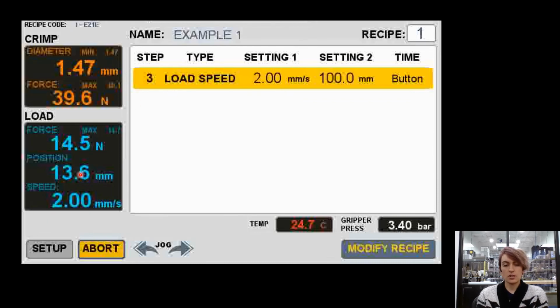We can see that the loader is moving forward, and it's trying to maintain this speed of 2 millimeters per second. And that means that we have a 14 Newton pushing force on the loader right now as we're maintaining that speed. We can see it's still just plugging along, and it's just going to maintain this step until it reaches our set point of 100 millimeters. Then that'll be the end of the recipe. So at that point, the machine will open back up to that initial diameter step that we set as step 0 on our recipe.